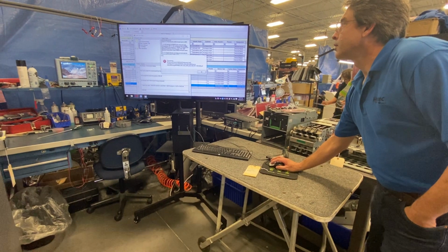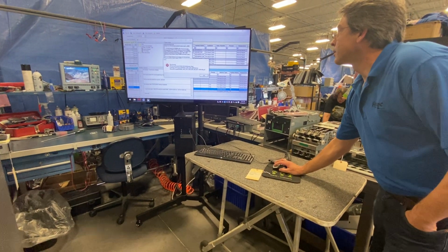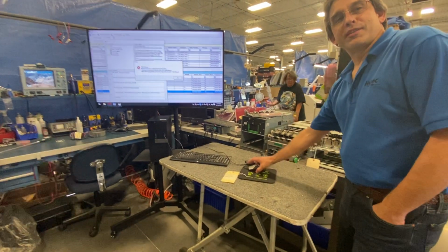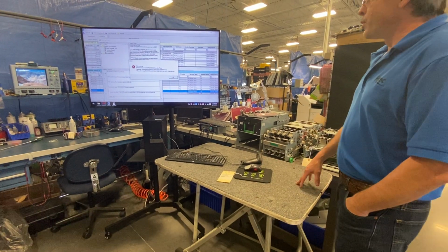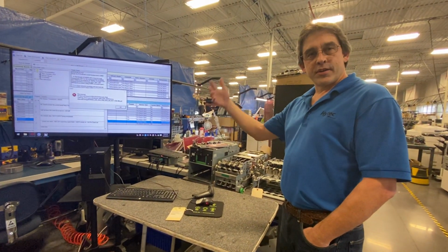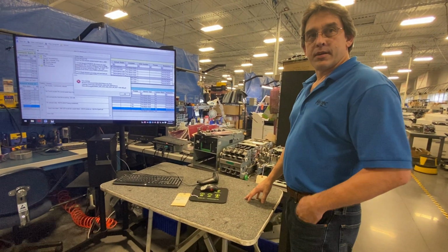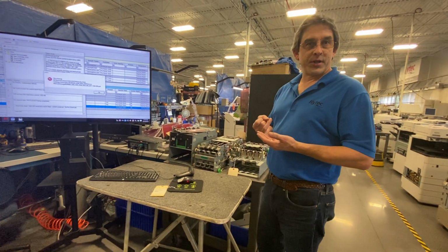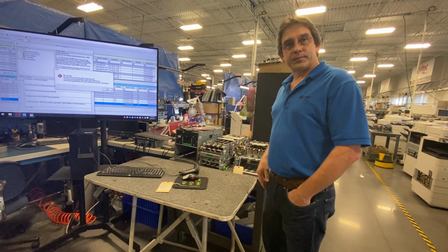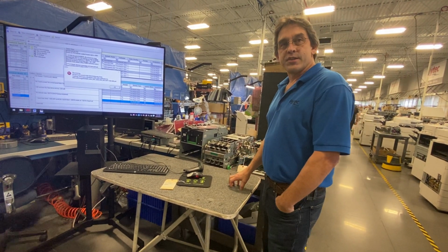Oh, there's manuals and everything in there. If I was tied to the network properly, you'd be able to get to it. But all of our service manuals, all the OEM documentation is linked through here. So if there's an error code you're not familiar with, you just pull up the service manual and get all that information in.